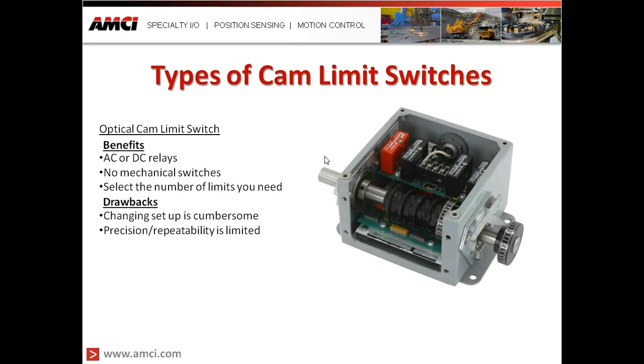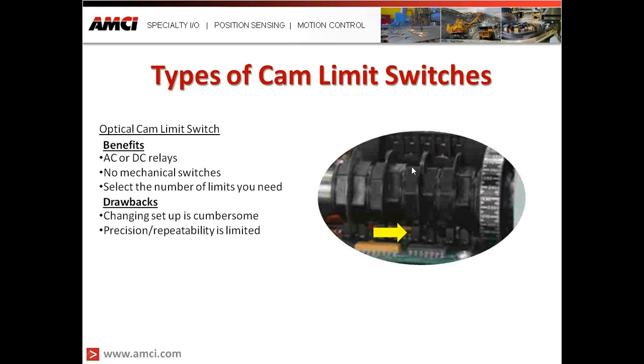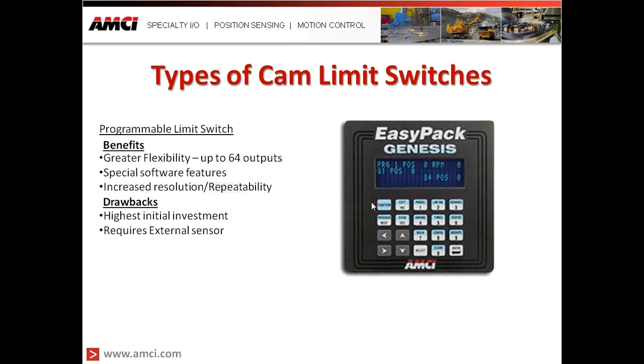The second option is an optical cam limit switch. You can select outputs based upon the type of loads you're switching, whether AC or DC. There are no mechanical switches, so no components to wear out. Just like the mechanical unit, you can select the number of limits you need. The drawback is that setup is cumbersome — you still need a wrench to adjust those lobes for on/off points, and precision and repeatability of the system is limited.